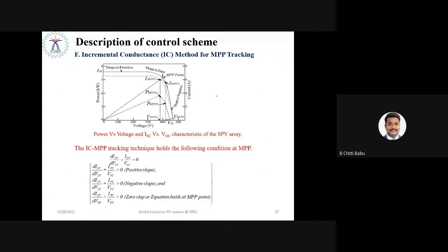Right. This is the MPPT technique. All of us know that the point at which we extract maximum power is the MPP. So this point must always be in equilibrium, having the slope zero. It implies that with any changes in irradiation or temperature, this point should not be shifted upwards or downwards. So we employ the incremental conductance method, where the change in current with respect to the change in voltage must always be zero. That is, the slope must always be zero. So if it is positive, it implies that the change is less than zero. If it is greater than zero, then the slope is negative. But it should always be at the equilibrium point that holds at the MPP. Then we are able to implement the maximum power point tracking algorithm by satisfying the maximum power transfer theorem.